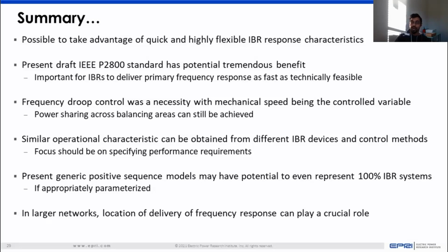We can also go beyond traditional frequency droop control because we can leverage the flexibility that these inverter-based resources provide, and this can be achieved even across wide balancing areas, where you can ensure that each balancing area is picking up its own burden of the generation imbalance.